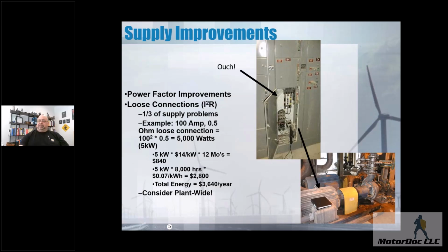So yeah, when we opened up to do our monitoring, we caught that right away. And, you know, is this a one-off? No, we just ran into another one just last month. So it happens more often than you think. Putting in the right fuses and things like that are going to save you a lot of problems. We're going to cover pumps in a few minutes because that was another big area.